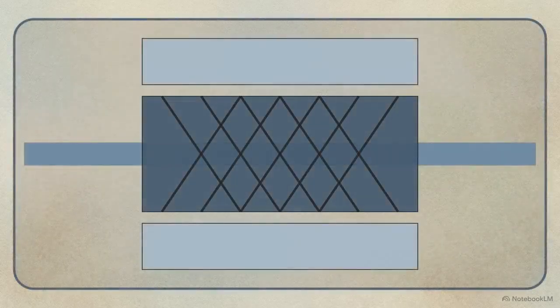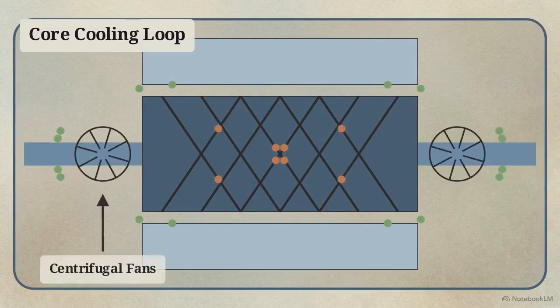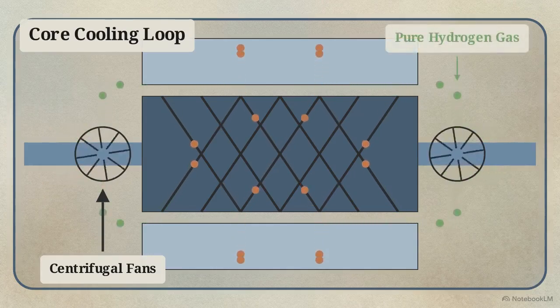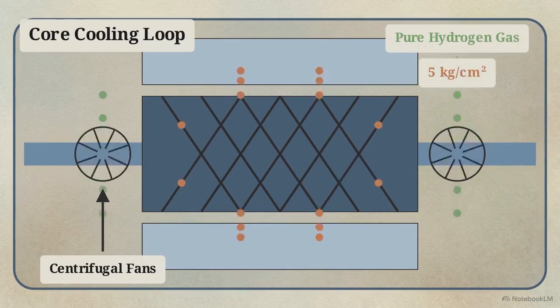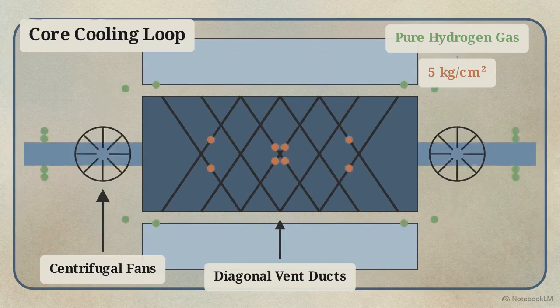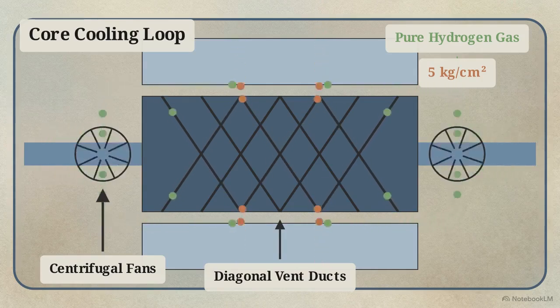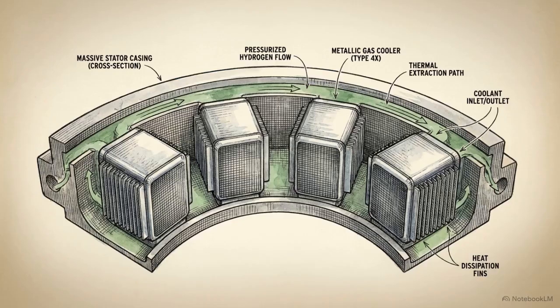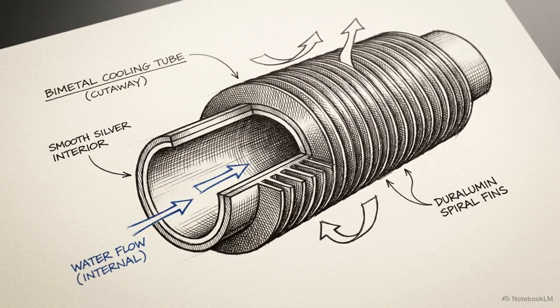The green path tracks the core cooling loop. Centrifugal fans mounted directly on the spinning rotor pull pure hydrogen gas, pressurized to 5 kilograms per square centimeter, forcing it through diagonal vent ducts. To reject this heat, the hot hydrogen cycles through 4 internal gas coolers, positioned at the end parts of the stator casing. These use bimetal tubes, smooth German silver on the interior for water flow, and ribbed duralumin on the exterior to maximize gas contact area.